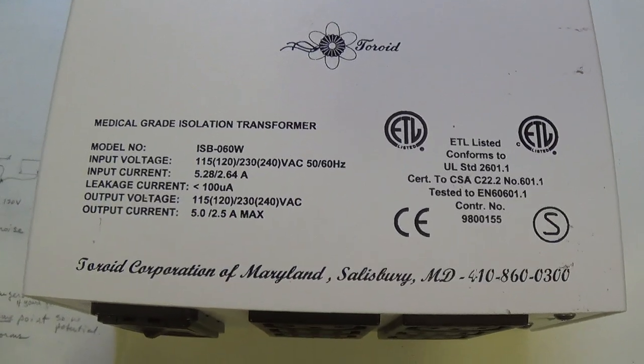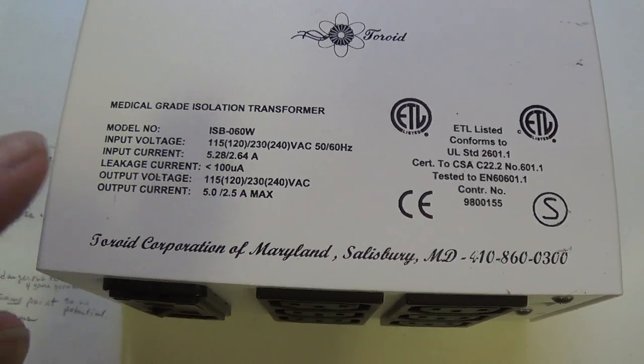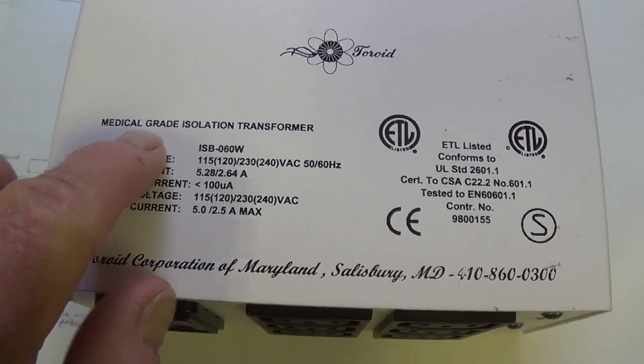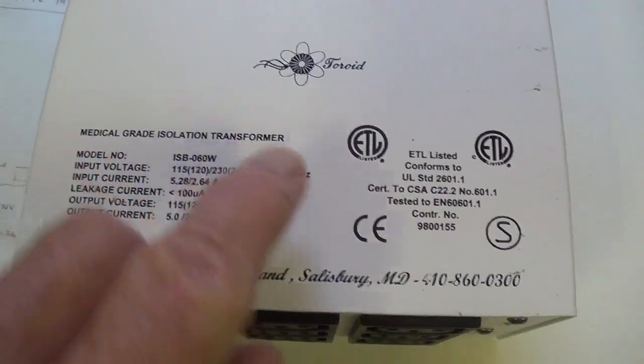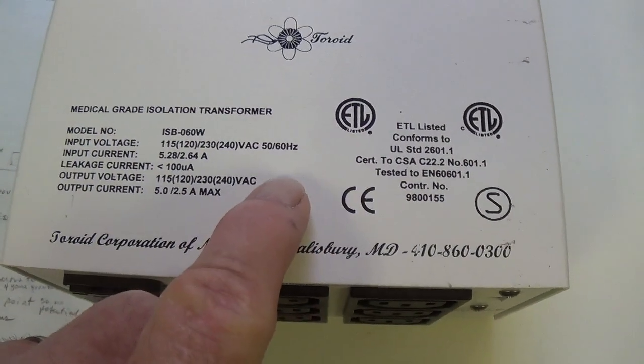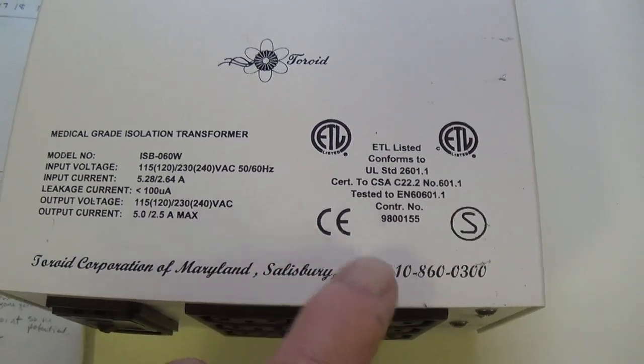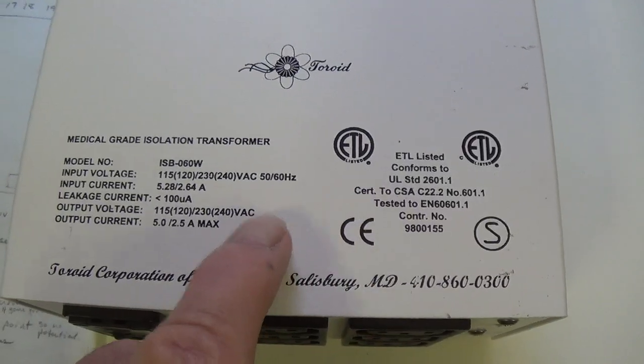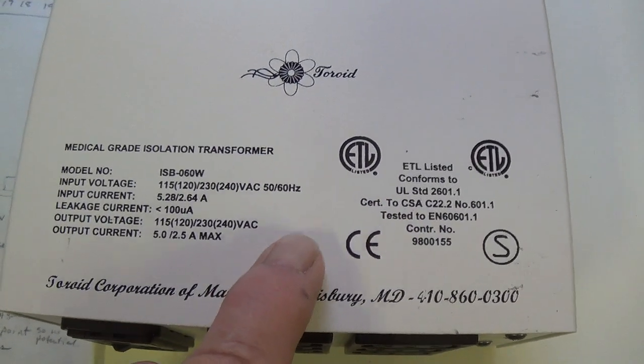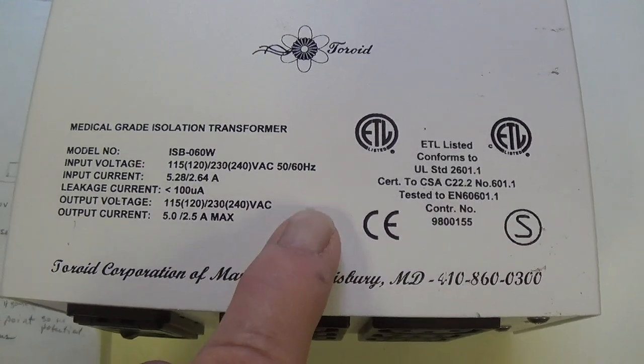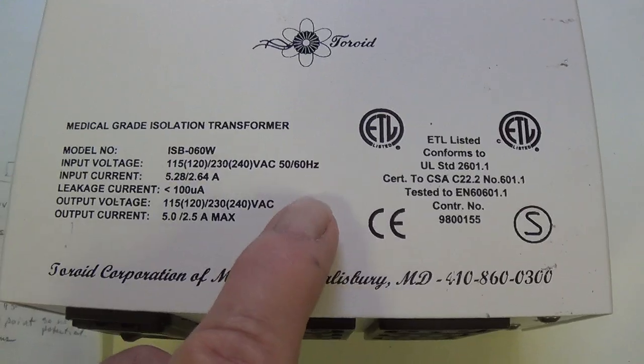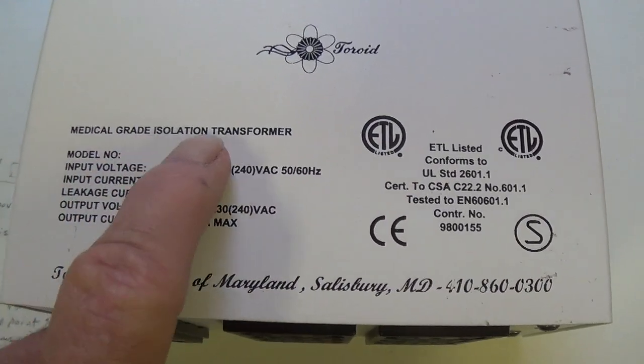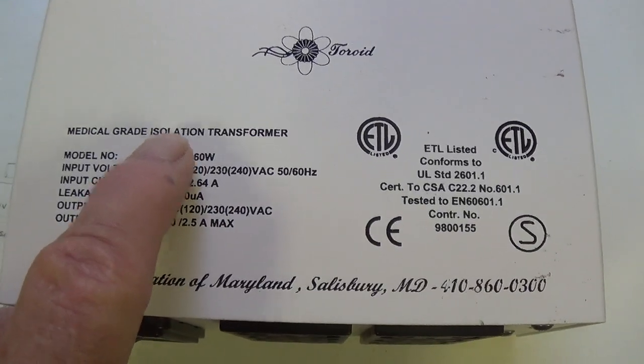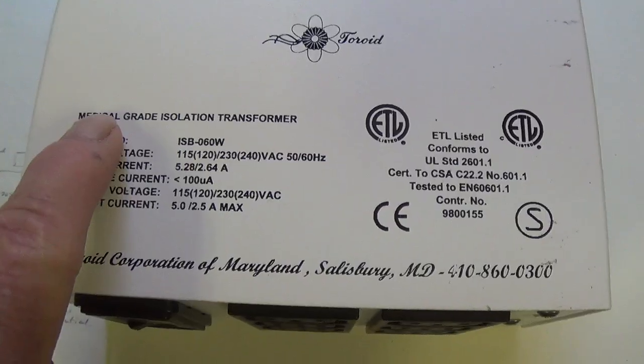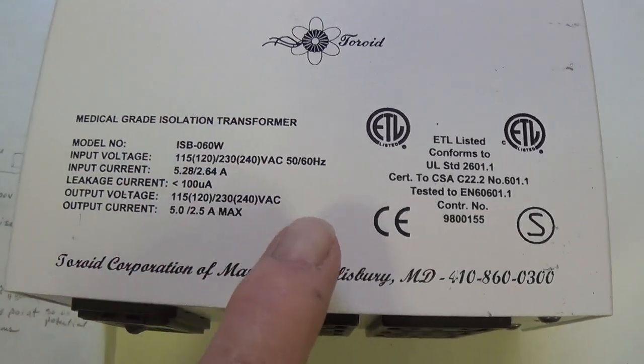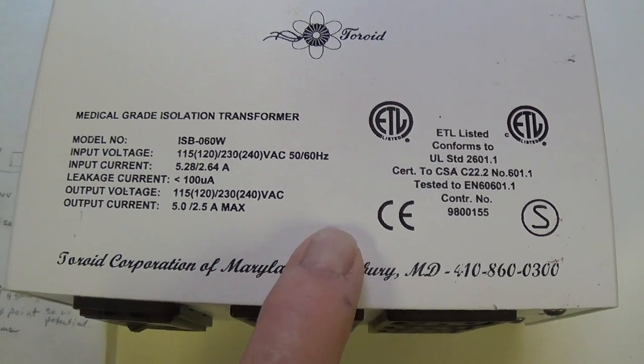Well, that's all just fine and dandy, but it doesn't work for us because that type of medical grade isolation transformer will have an internal connection between the neutral return line and ground. Okay, that will make it not suitable for our use with our oscilloscopes. Fortunately, however, that problem can be easily remedied. So you can convert a medical grade isolation transformer that is really for isolation from electrical noise into a tech grade isolation transformer that effectively isolates you from ground reference.